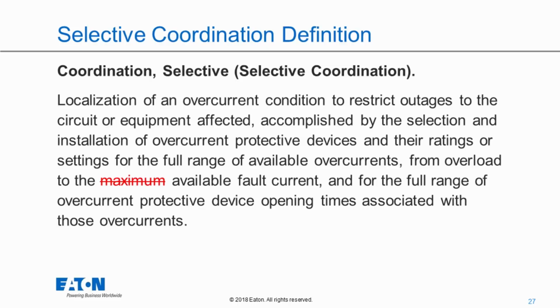So, for those of you who perhaps are new to selective coordination, when it comes to compliance, we have to consider all times and all currents, so up to the available fault current. So if you think time current curves are the only thing that might be required, that may not be the case. You also may need to consult manufacturer selective coordination tables or charts.